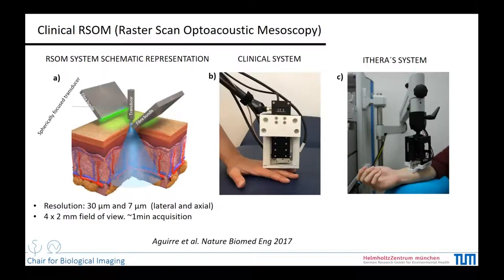In my group we have been developing clinical raster scan optoacoustic mesoscopy for a few years. To do RSOM, we use a transducer that is raster-scanned on top of the skin while we illuminate using a pulsed laser. At each point of the raster scan we acquire A-lines, which are combined to form the 3D image. The system can obtain images with a lateral resolution of 30 micrometres and an axial resolution of 7 micrometres, with an acquisition time of around one minute for a field of view of 4 mm by 2 mm. This system was taken by Ithera and further developed into their clinical system.